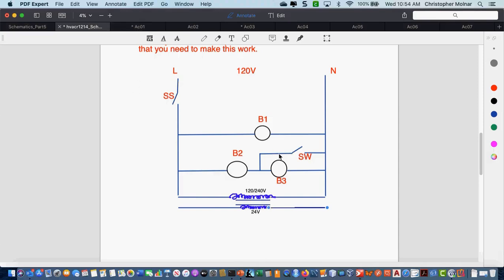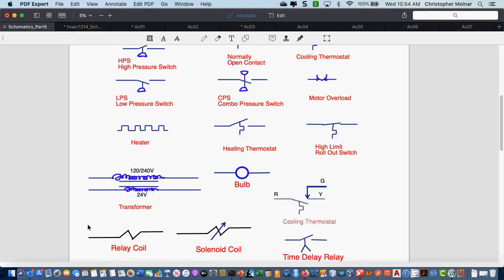So down here on the bottom, I need to put in a switch. Basically, I'm going to move my switch from up there, because I need to put in my 24-volt switch. I'm no longer dealing with a line voltage switch. So let's go ahead and draw in the change to this circuit. Okay, coming out of the switch, what do I need to have? Your relay coil. You have a relay coil.